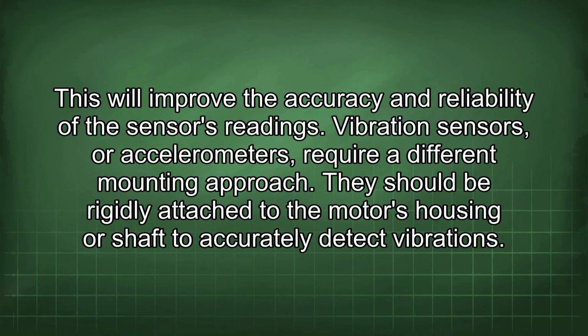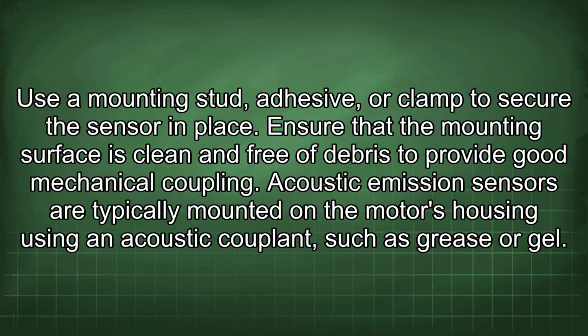Vibration sensors, or accelerometers, require a different mounting approach. They should be rigidly attached to the motor's housing or shaft to accurately detect vibrations. Use a mounting stud, adhesive, or clamp to secure the sensor in place. Ensure that the mounting surface is clean and free of debris to provide good mechanical coupling.